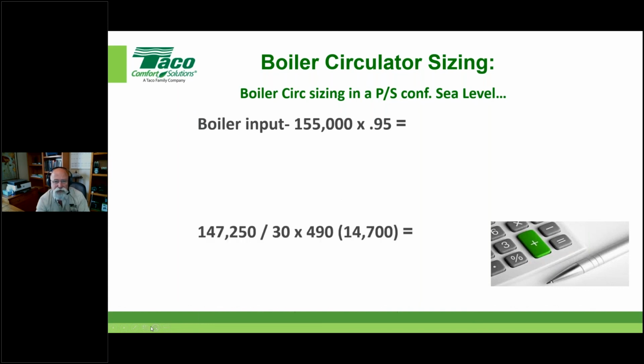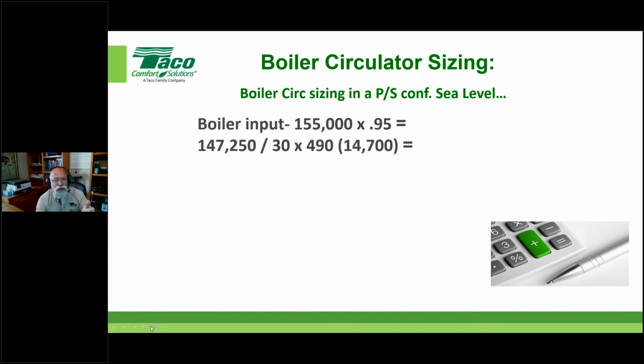All right, you see where I'm going with that. So here it is, real quickly. Let's take the same 155 at a high efficiency AFUE of 95%. Here's the math: 147,250 is the result of this calculation, divided by — just for teaching purposes — a 30-degree delta T. I take my 30 times 490, gives me 14,700. So the result of this divided by this — anybody want to spit it out real quick?